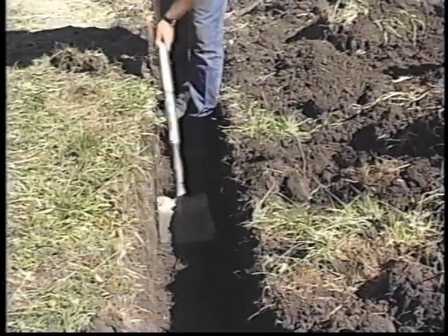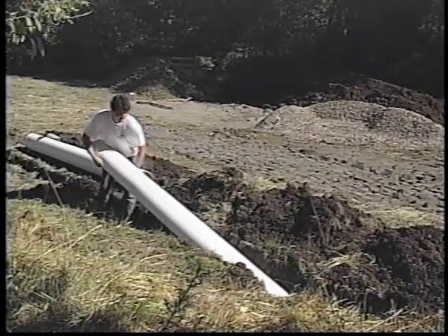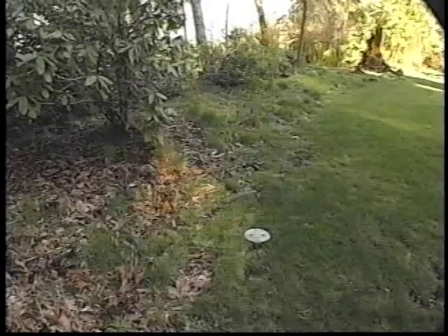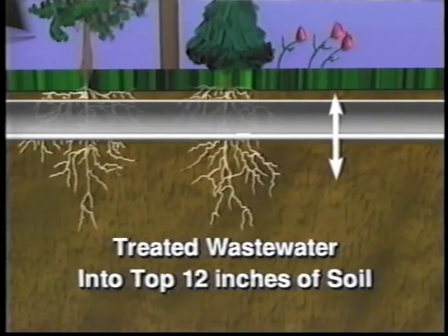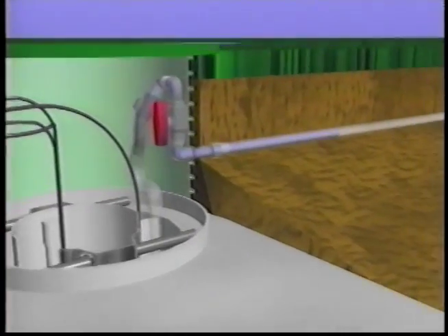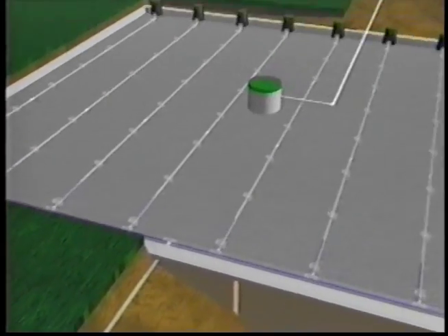Such shallow trenches are often only one-tenth the length of a conventional drain field, and one-third to one-half the width. This makes installation in sensitive sites easier, and eliminates the need to destroy existing landscaping or trees. Placing the treated wastewater into the top 12 inches of the soil — where a majority of soil organisms live and where plant roots drink — allows final polishing, bacterial reduction to near zero, and the potential for substantial nitrogen reduction. Advanced wastewater treatment with an ISF system protects public health and the environment.